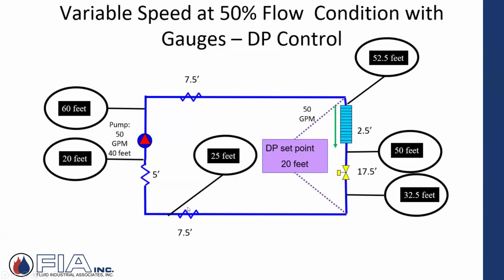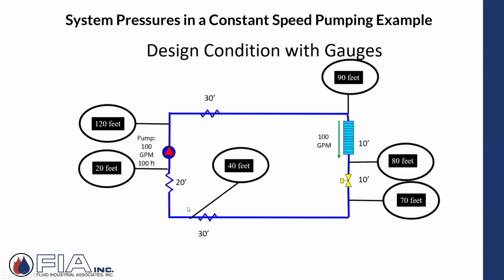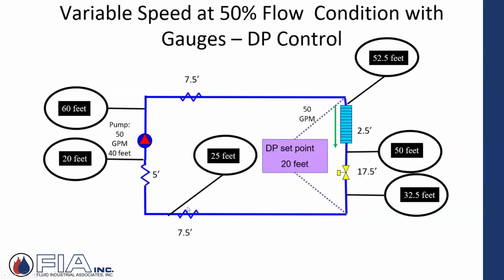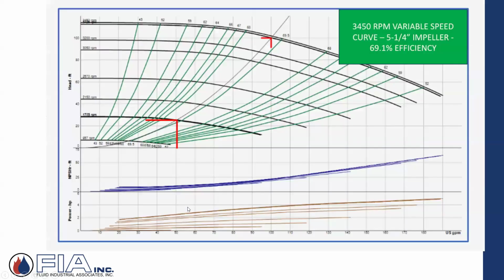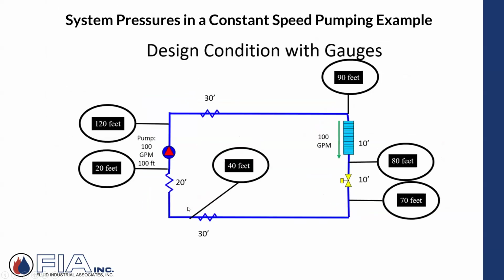And again, we talked about it before, variable speed, what's happening? As I reduce that flow, my pressure drop changes, right? The original we talked about before, the 30 feet of head, the 10 feet of head at 100. As I reduce that flow, my pressure drop changes. But I still have what they call a control head, if you will, a DP control. So differential pressure set point. In this case, maybe I've picked it at 20, and that's a function of the 10 feet of pressure drop and the 10 feet on the control valve itself.